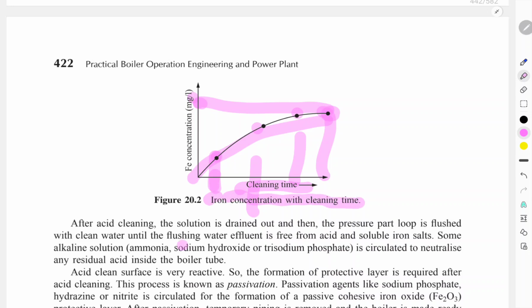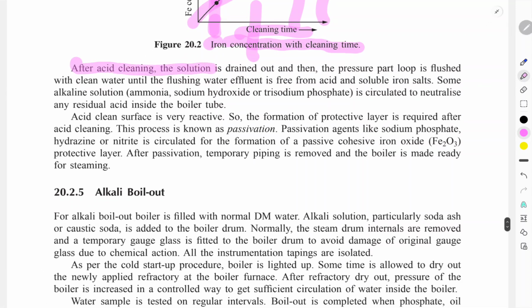It is very important. Okay, so after the acid cleaning, the solution is drained out. Then the pressure parts of the loop are flushed with clean water until the flushing water is free of acid solution and iron salt. Some alkaline solution, such as ammonia, sodium hydroxide or trisodium phosphate, is circulated for neutralization of residual acid inside the boiler tube. The acid cleaned surface is very reactive, so formation of a protective layer is required after the acid cleaning. This process is known as passivation.